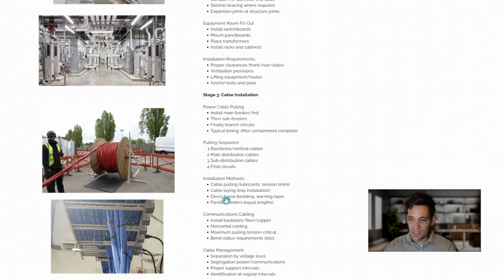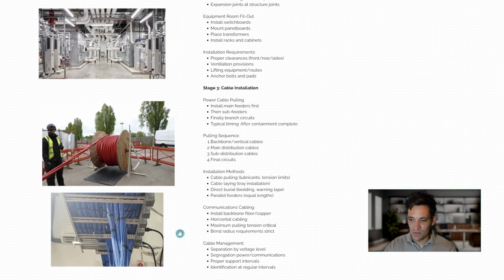If it's direct buried, we would have had to do this as part of the civil works, or if it's done through conduits, we may use a winch as well, or some sort of mechanical aid, depending on how big the cables are, how tough they are to install. And it's essential during this stage, again, that we're separating power and communications cable and we're identifying our cables. We're writing the name on them, the location, where they run to, so we're not wasting time retesting everything and trying to work out where all the cables have been run.